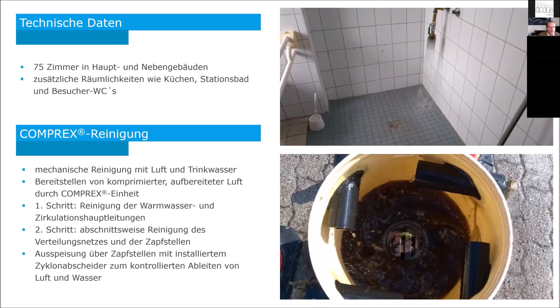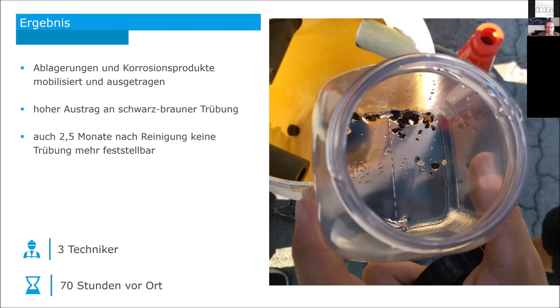To be fair, it must be said that this is often a collective result, because when we clean galvanized systems, subsequent turbidity can logically occur since the surfaces remain corrosive. In this case, the addition of inhibitors is often typically necessary. In many cases, the inhibitor dosages are already present, and only after the cleaning does the issue of turbidity due to fixation on the walls also disappear.